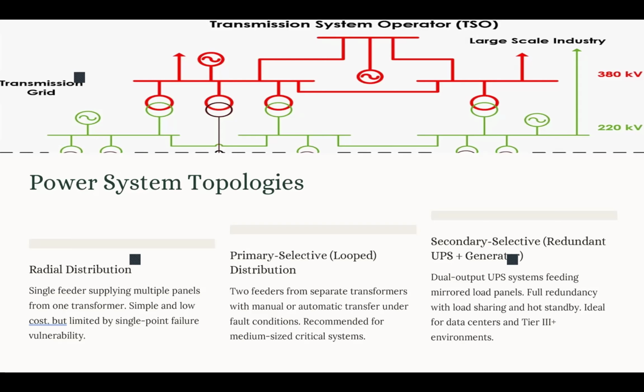Now, we could have another type of topology that we call primary selective distribution. In this topology, we now have two independent feeders. They are connected to those panels as redundant of each other. So if one gets out, the other one kicks in and starts powering the system. So the problem that we had, if we have a fault in a feeder, now we don't lose the supply. Or if there's a high disturbance in feeder number one, we could manually or automatically transfer to feeder number two and make sure we're meeting the criteria for the power system.